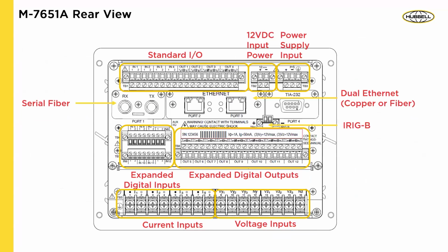On the back side of it, this is turned on its side now, so you can see it better. Outputs. Let me see if I can get a laser pointer. Right, so that's your standard IO, your 12-volt input power if you want to power it up with 12 volts. Or there's a power supply for low voltage DC, high voltage DC, or your regular AC supply. Your serial fiber, dual Ethernet, copper or fiber, could be both. And then we also have IRIG-B here. We have additional expanded digital inputs and expanded digital outputs. These are optional, so if you wanted more inputs and outputs, you could have them. And then at the bottom, you have your current and voltage inputs.